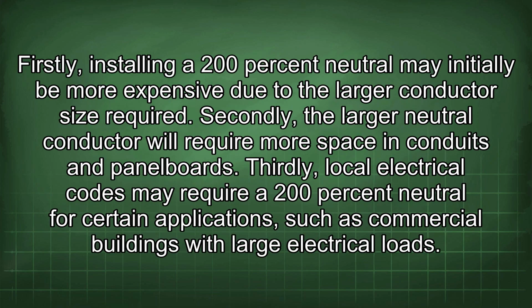Firstly, installing a 200% neutral may initially be more expensive due to the larger conductor size required. Secondly, the larger neutral conductor will require more space in conduits and panel boards. Thirdly, local electrical codes may require a 200% neutral for certain applications, such as commercial buildings with large electrical loads.